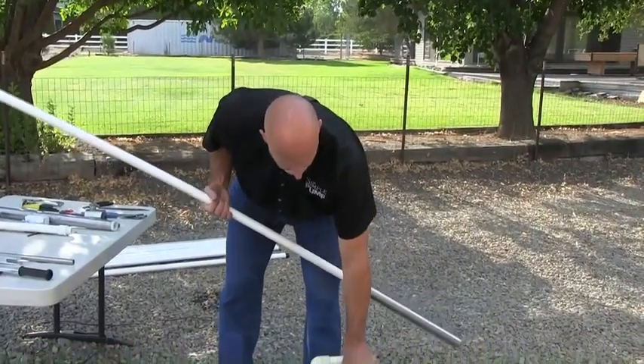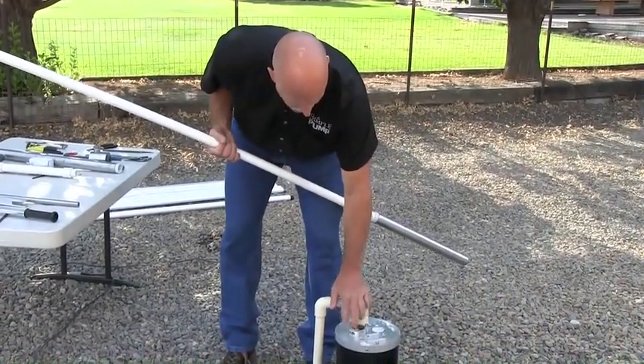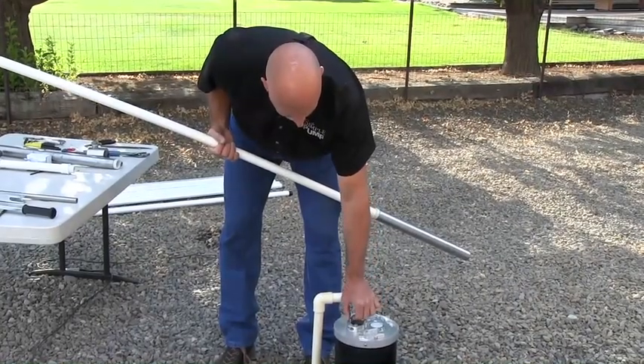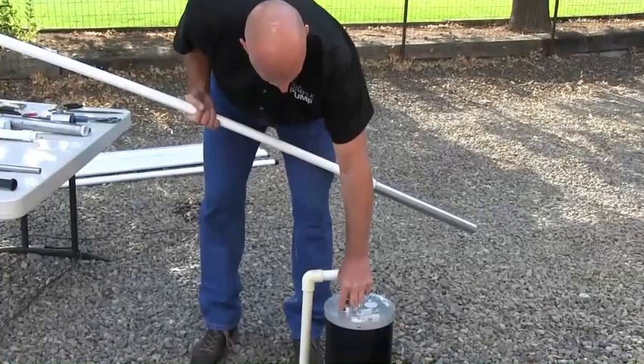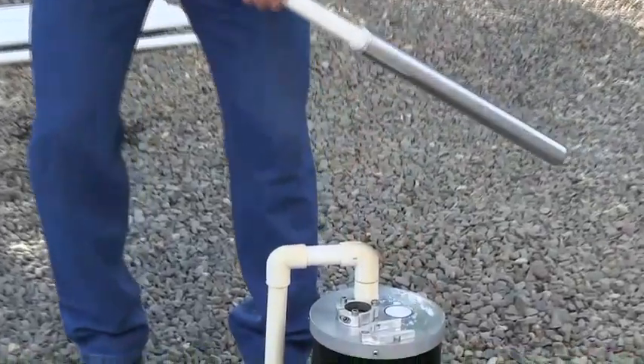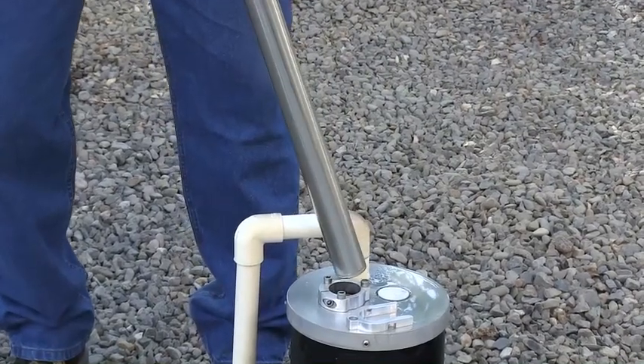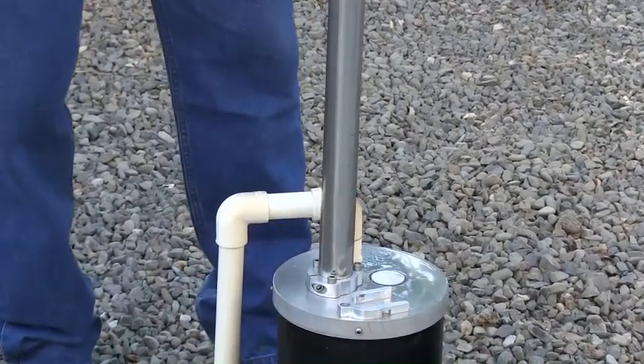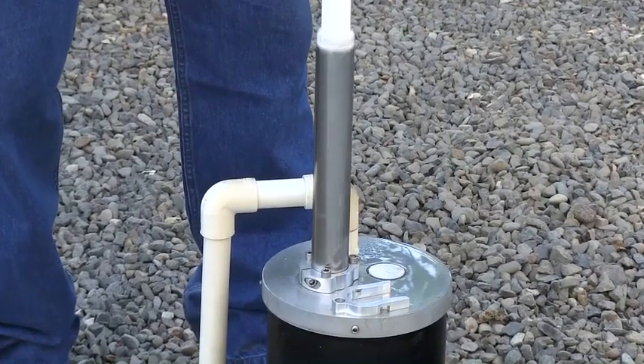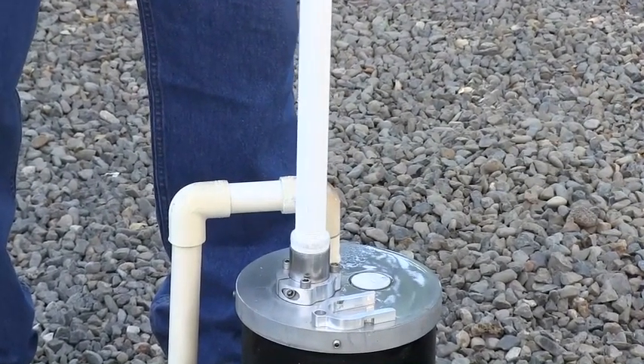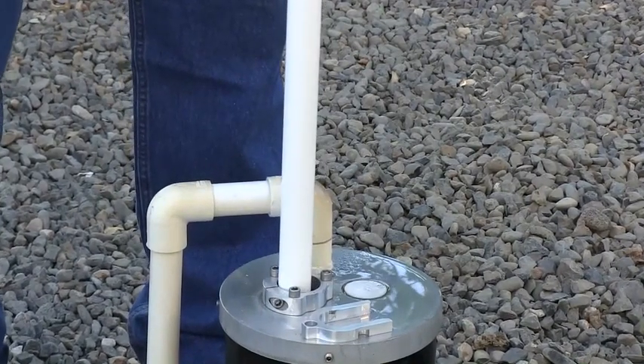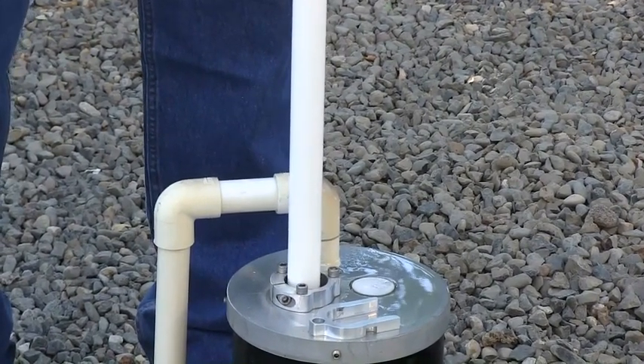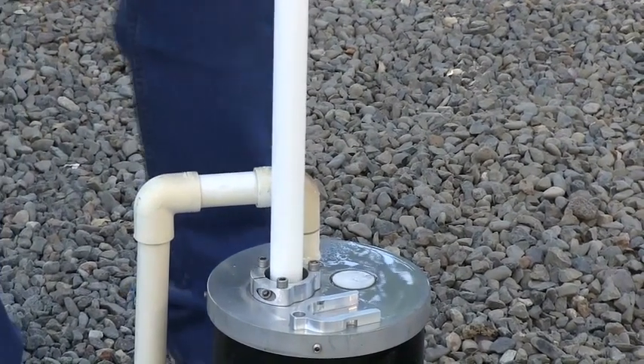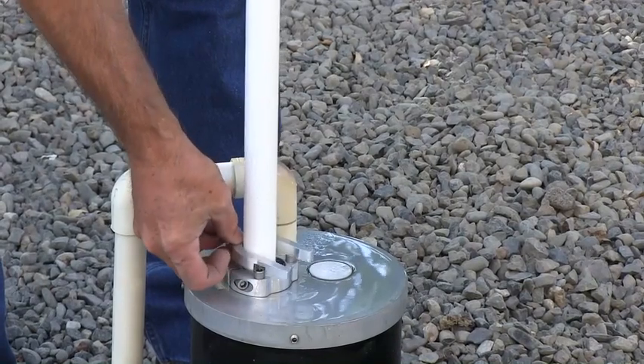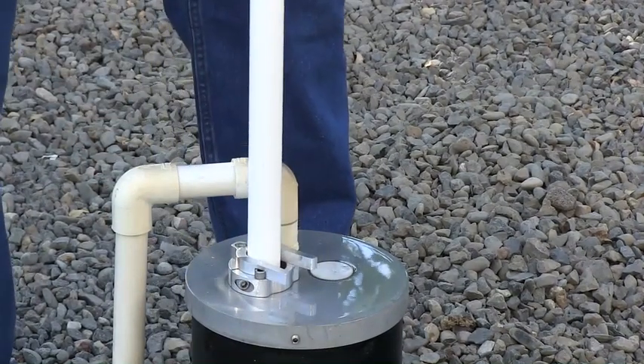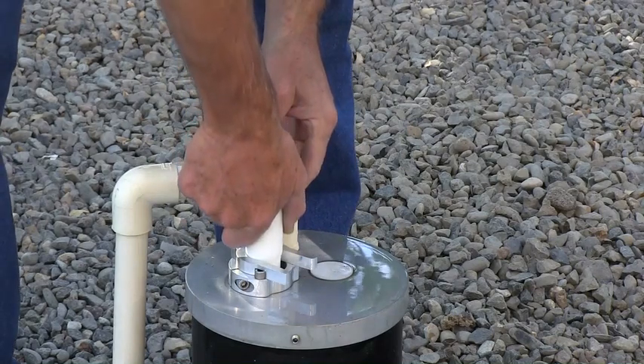We're going to introduce the simple pump system through the split flange that's mounted to the well cap. The 3 bolts on the top of the split flange should be slightly loose, and the pinch bolts should be loose. Then we're going to have our safety tool handy, and we're going to introduce the pump cylinder through the split flange. Now there's a 224 Buna rubber O-ring in there that might provide a little bit of restriction, but you have to deal with that, perhaps using a little Vaseline or something if it's more difficult to introduce.